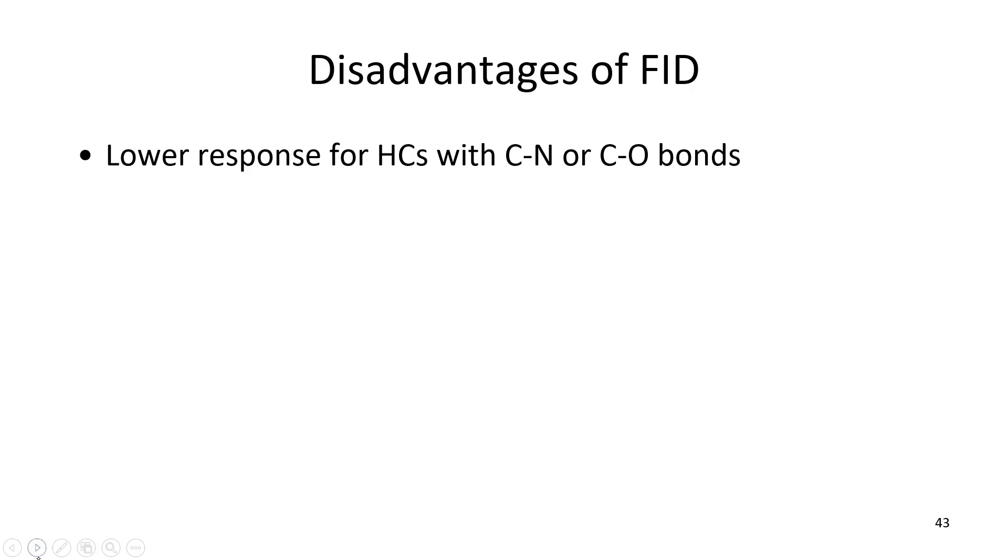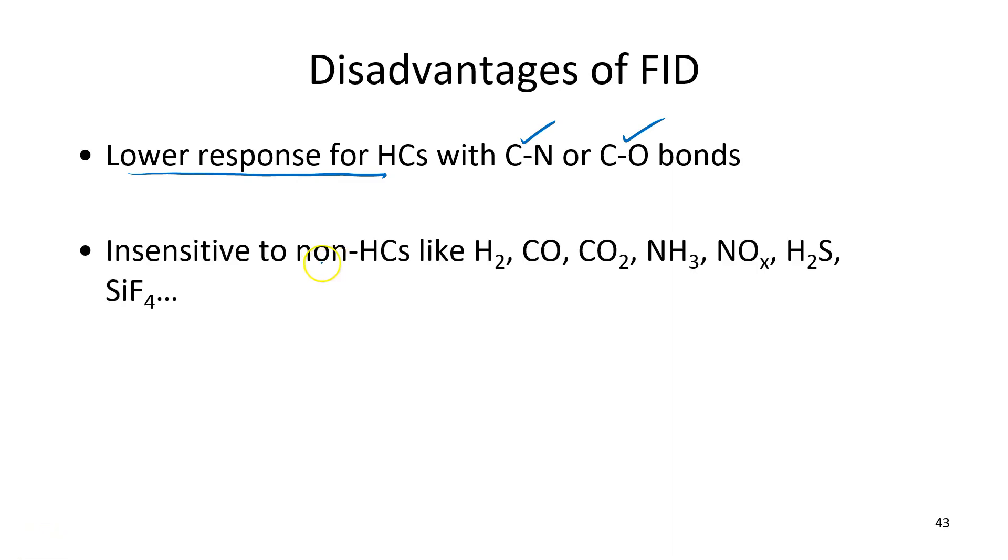Some disadvantages are that it doesn't respond that well to hydrocarbons with CN or CO bonds. It won't respond at all to non-hydrocarbons like the ones shown here. So really, the FID is not universal like the TCD was.